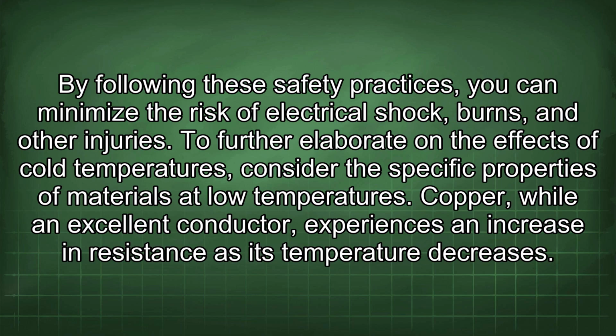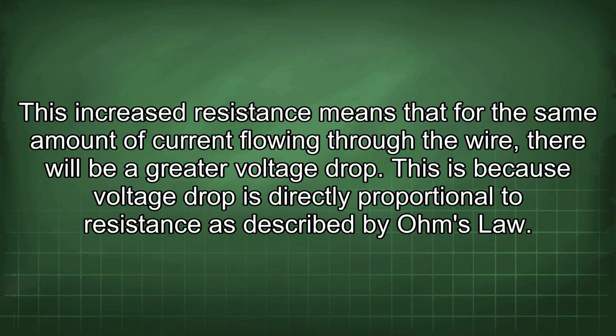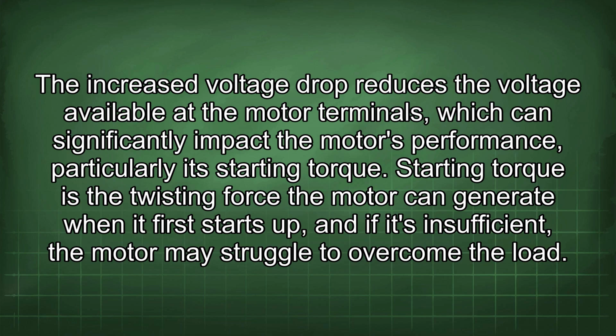To further elaborate on the effects of cold temperatures, consider the specific properties of materials at low temperatures. Copper, while an excellent conductor, experiences an increase in resistance as its temperature decreases. This increased resistance means that for the same amount of current flowing through the wire, there will be a greater voltage drop. This is because voltage drop is directly proportional to resistance, as described by Ohm's law. The increased voltage drop reduces the voltage available at the motor terminals, which can significantly impact the motor's performance, particularly its starting torque. Starting torque is the twisting force the motor can generate when it first starts up, and if it's insufficient, the motor may struggle to overcome the load.